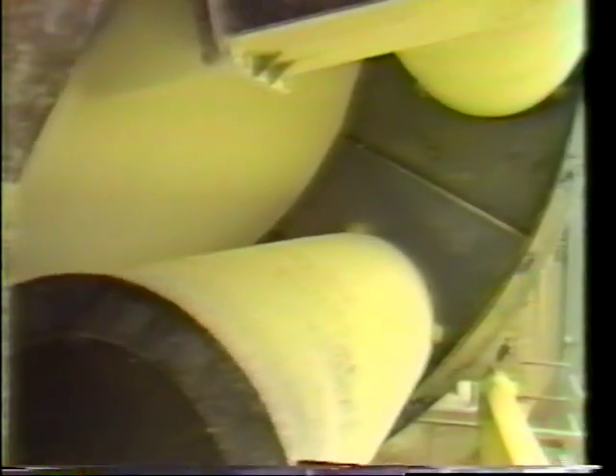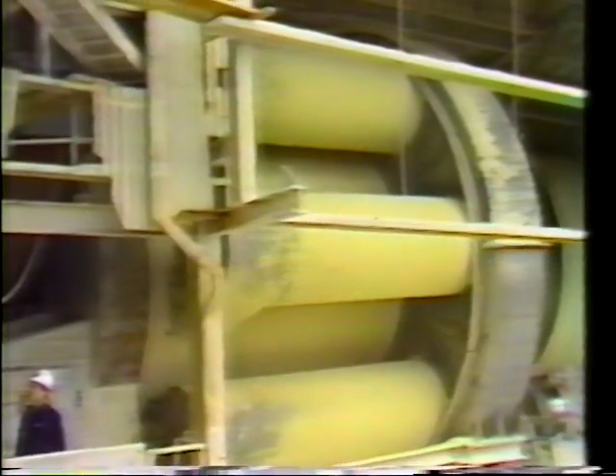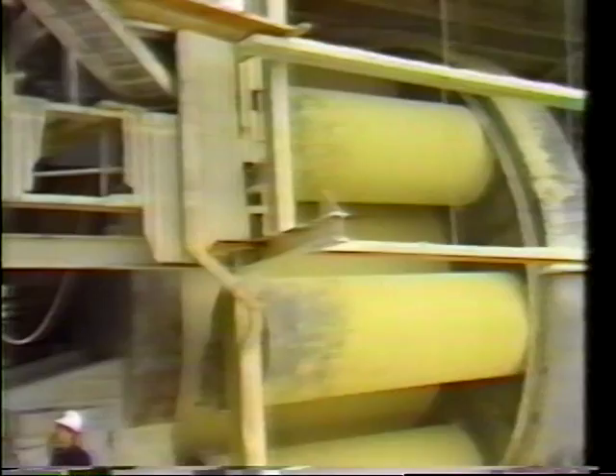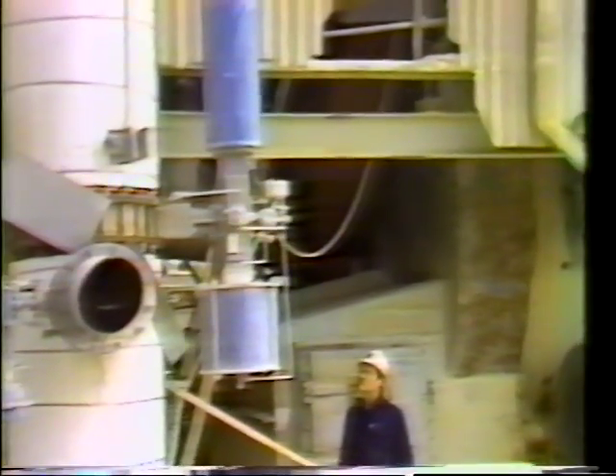Shown here are the kiln's heat exchangers where the 600-degree Fahrenheit drying gas is obtained for the Williams DF pulverizer. This heat is required to dry the 15 percent surface moisture from the coke during the grinding operation. The hot gases exit from the top of the firing end of the number two kiln and are conveyed through this 24-inch diameter duct past a tempering air damper. This damper allows fresh air to enter at this point if the system temperature goes too high.